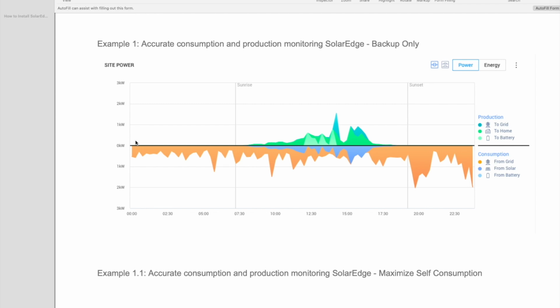Okay, lastly, once you have online data to look at, there's a few things to look at in these graphs to understand if the CTs are installed correctly or not. So right here is an example of accurate consumption and production monitoring with backup only. You'll see consumption just kind of bounces around under the line there. It doesn't change when the sun comes up or goes down. It just starts taking consumption from the solar rather than from the grid.